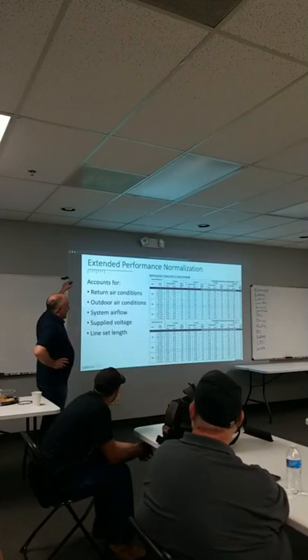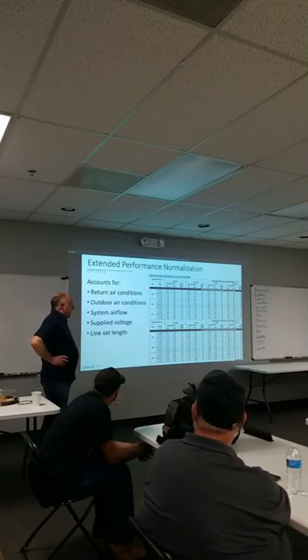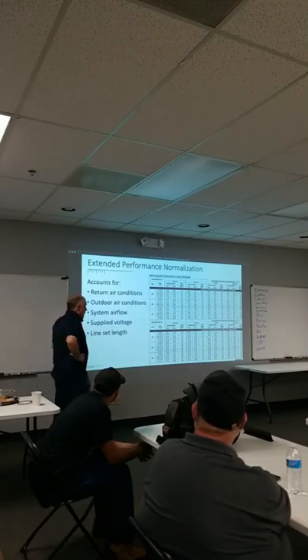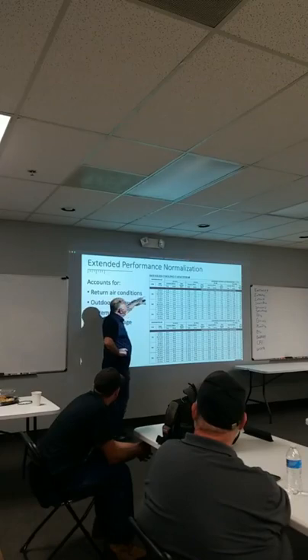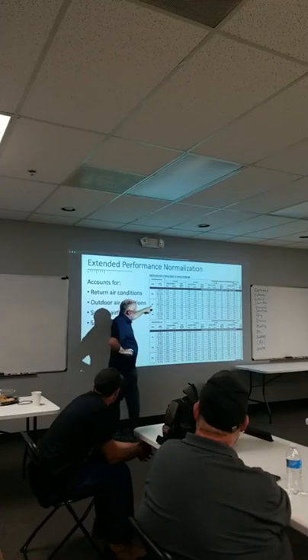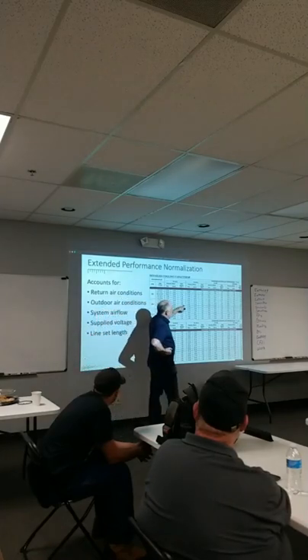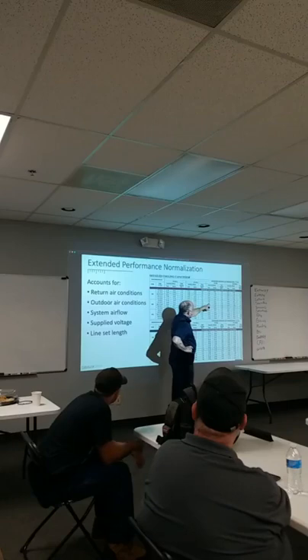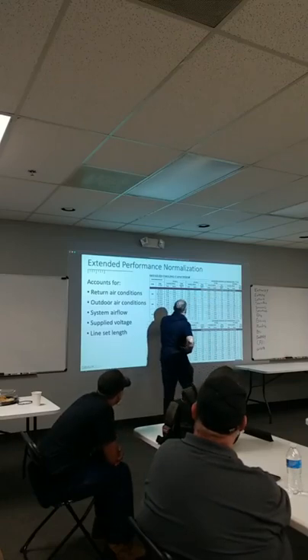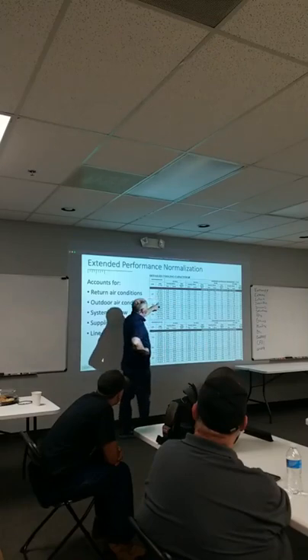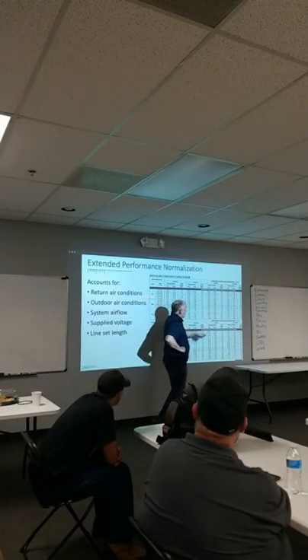Another interesting thing is normalization, right? And here's an interesting fact: when we're looking at, like, this is a 1.5 ton system, okay? So it's got a 600 CFM standard capacity. If we run this all the way out here, this 18,000 BTUs, this is a 95-degree day, right? Condenser air 95. If we go here, this is a 67-degree wet bulb, 67, and go out here, it's 18,000 BTUs.